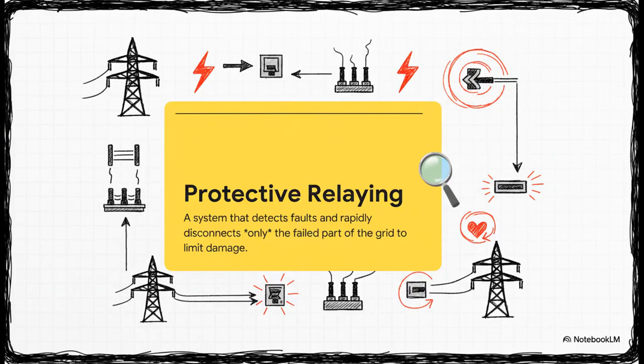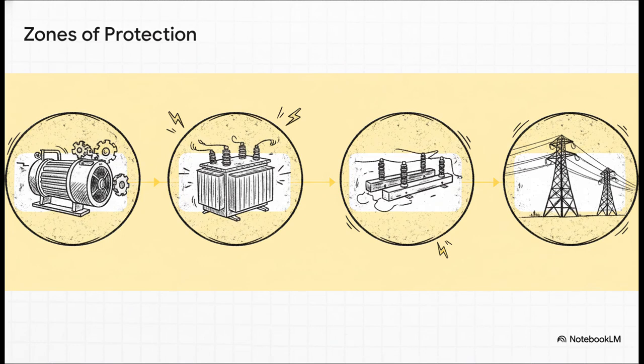So what is protective relaying? Well, it's a whole network of smart devices. These are the relays, and they have two main jobs. First, they sense when and where a fault happens. And second, they instantly send a signal to open circuit breakers and surgically isolate only the damaged part. The goal isn't just stopping the fault, it's doing it with the absolute minimum disruption to everyone else. The way it does this is pretty brilliant.